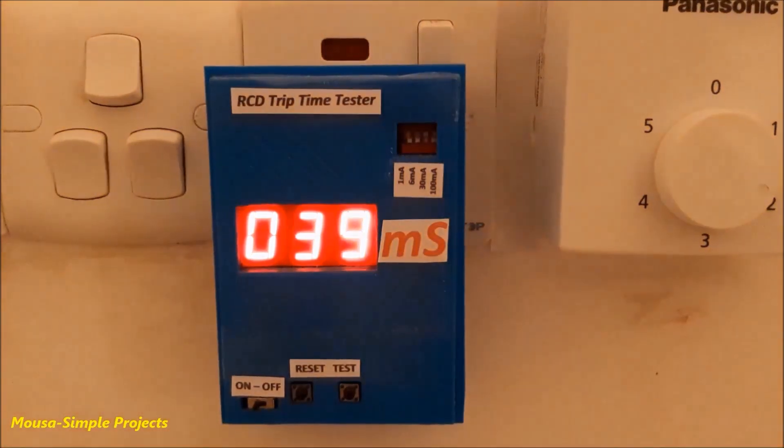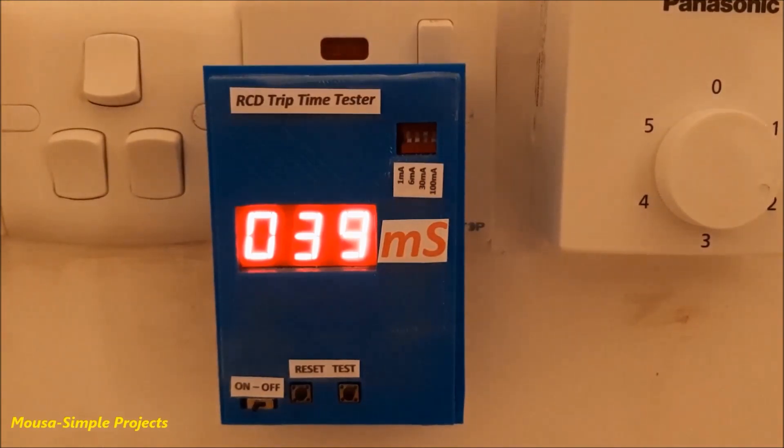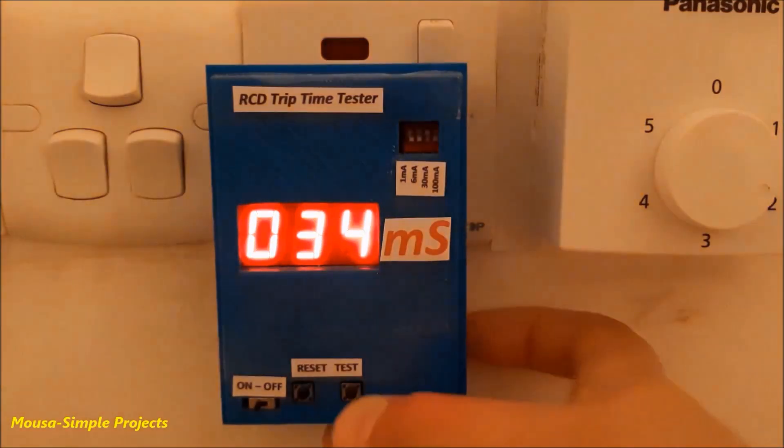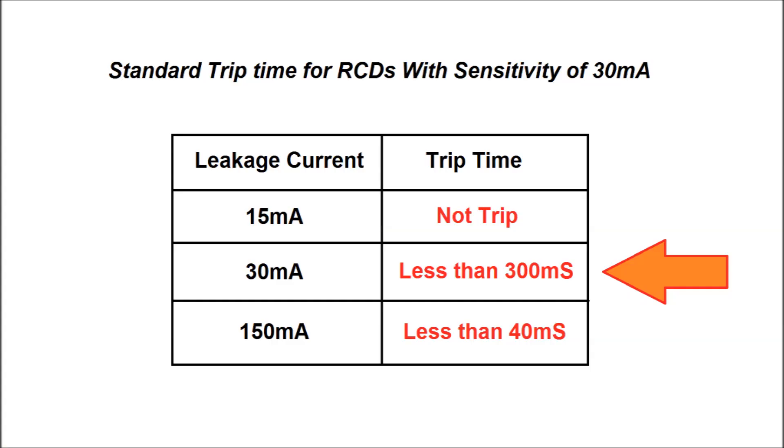This time, the reading number is 39 milliseconds, and one more time, 34 milliseconds. So according to this table, my RCD is working well.